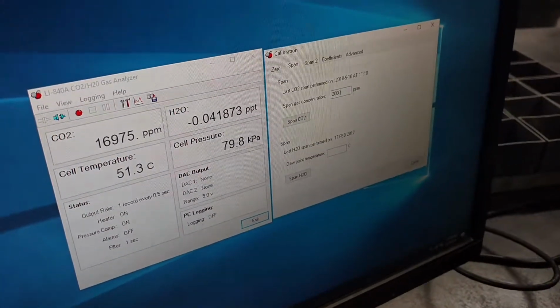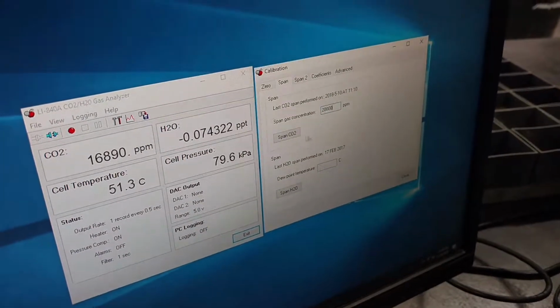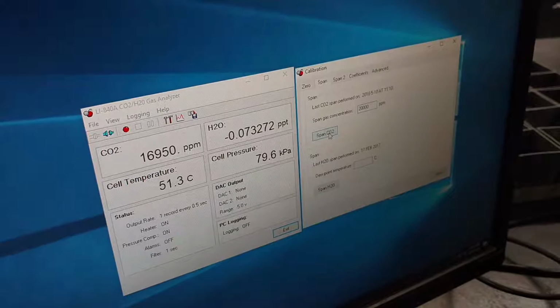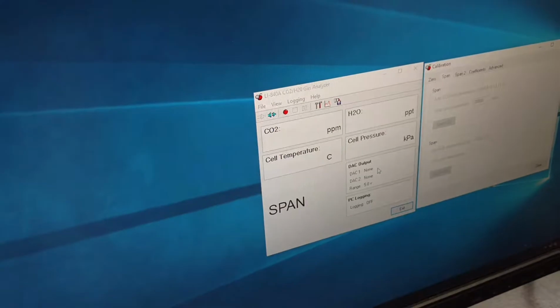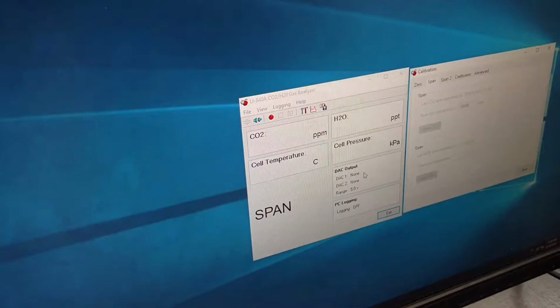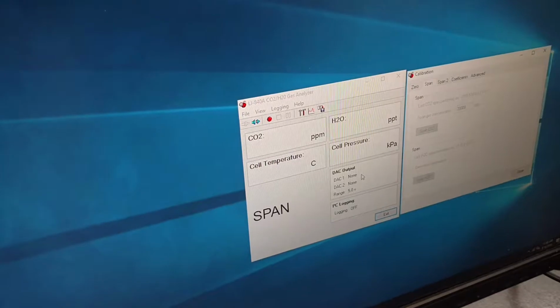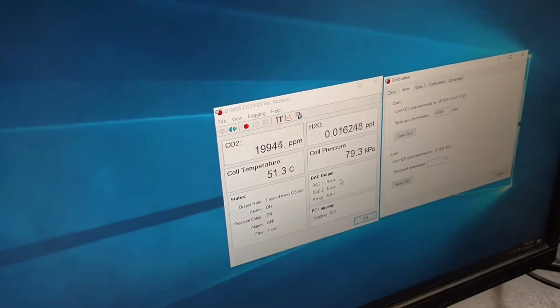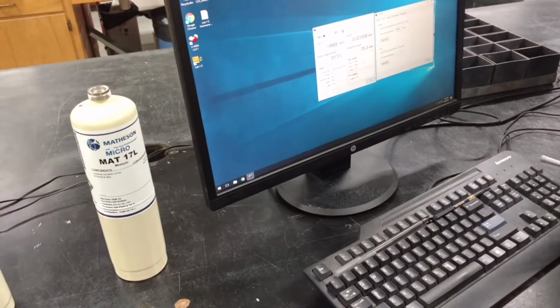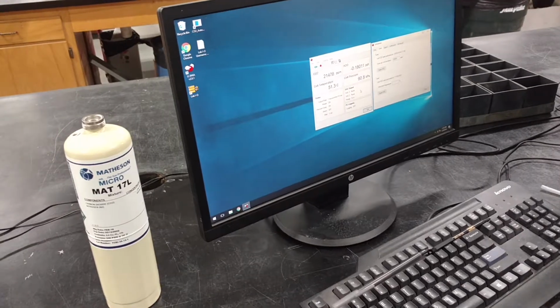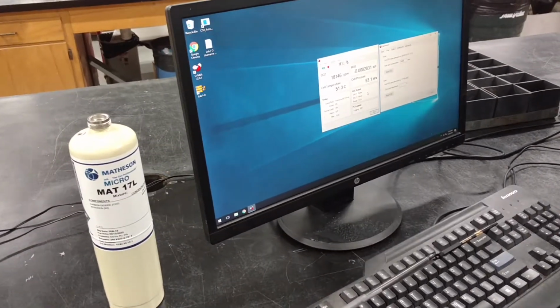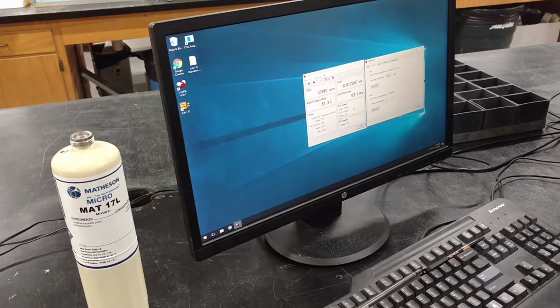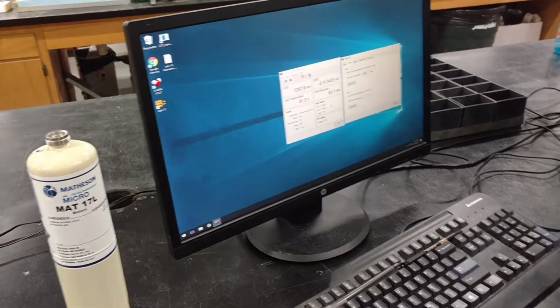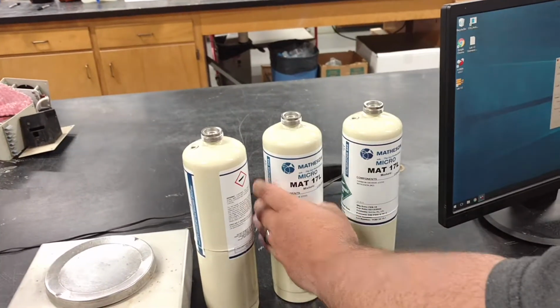You're going to enter the actual concentration of your calibration gas in parts per million. Since this is a 2% calibration gas, we're going to use 20,000 parts per million CO2 and click Span CO2. Once the Licor software has captured this middle point, you should notice the CO2 reading come back very close to your calibration gas concentration. With this middle point captured, you're going to want to disconnect the jar again from your SR-1 and remove the canister from the regulator to move on to your third calibration gas.